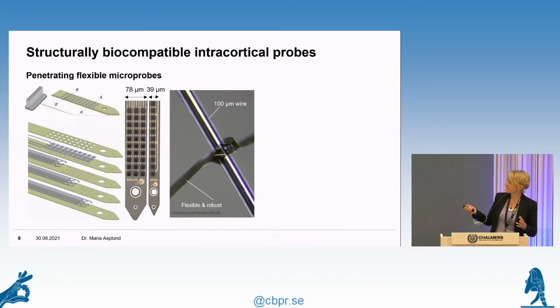So this is a multi-layer assembly. Each yellow film here is polyimide, and in between there's platinum, and then there's conducting polymer electrode materials here to boost the performance. The devices are extremely flexible, as we can see here, so you can really tie a knot with the device without damaging it. And they are also extremely small, so it's smaller than a human hair and still can have just one single shank, 30 electrodes and more on that shank.